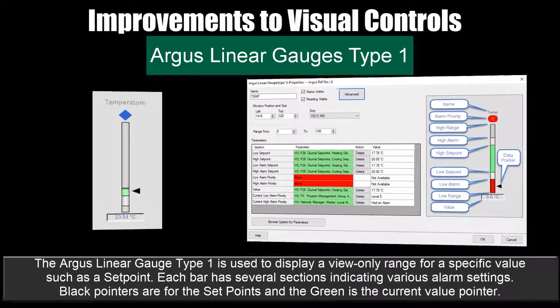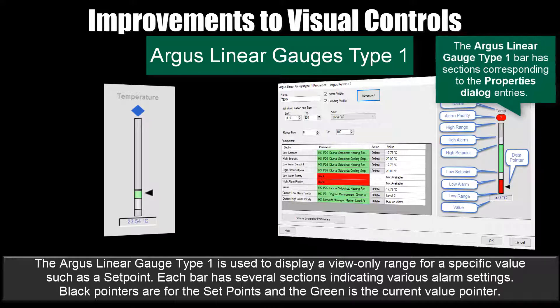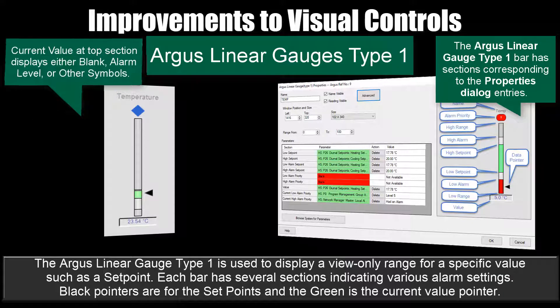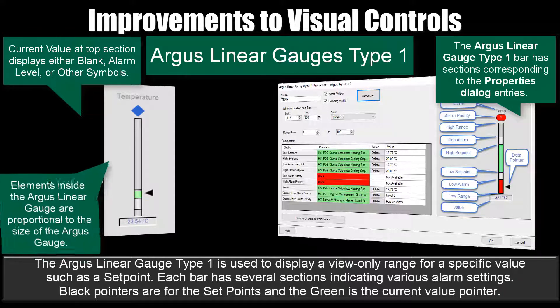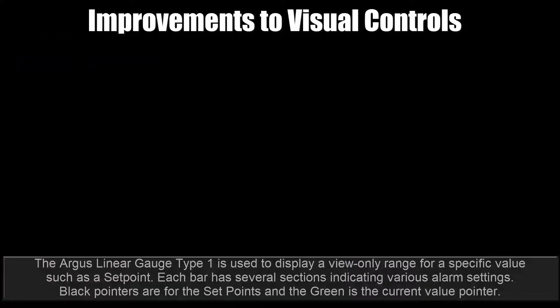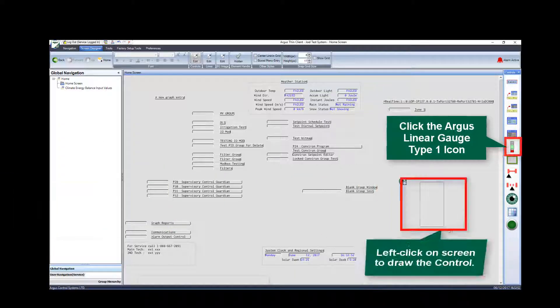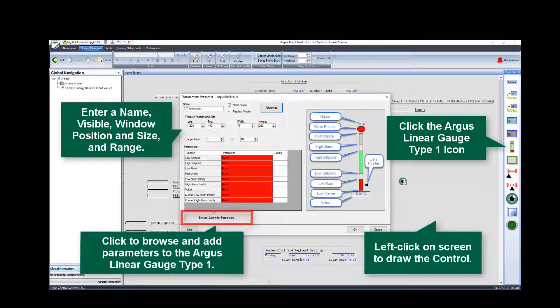The Argus Linear Gauge Type 1 is used to display a view-only range for a specific value, such as a setpoint. Each bar has several sections indicating various alarm settings. Black pointers are for the setpoints, and the green pointer indicates the current value. The bar has various sections that correspond to the properties dialog entries. Based on where the current value is, the top section displays either blank, alarm level, or other symbols. Each element inside the Argus Linear Gauge Type 1 is proportional to the size of the gauge. To configure: click the Argus Linear Gauge Type 1 icon, enter a name, visibility, window position and size, and range, then browse and add parameters.